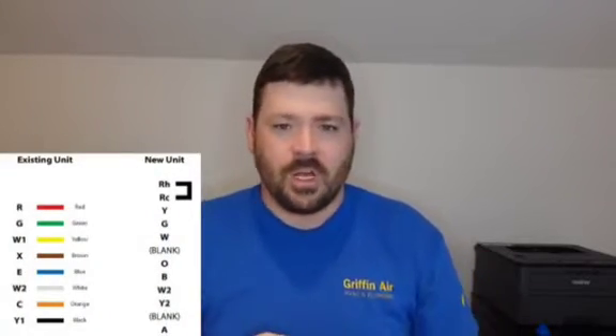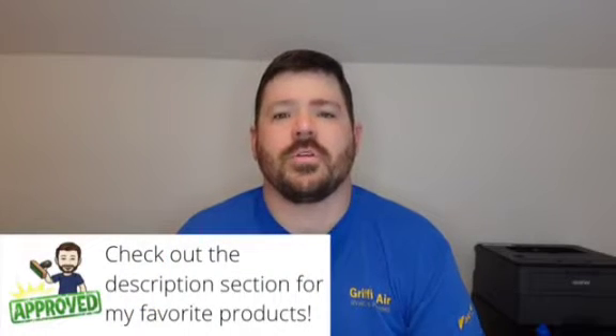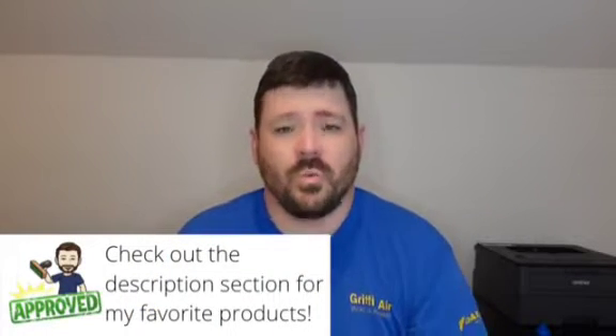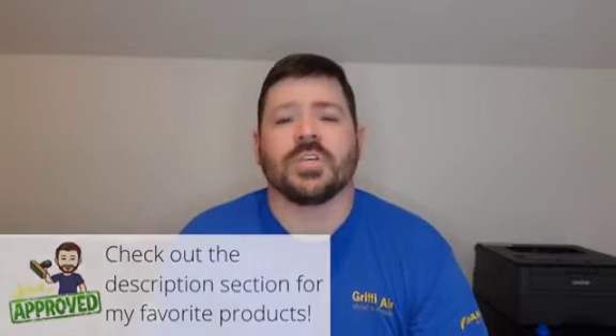When it comes to the common wire, I've noticed that different brands use different color common wires. Commonly, it's going to be usually black or blue. I have seen gray used before, but ultimately you want to keep that in mind if you are wiring in a new thermostat. Another example might be Trane and American Standard. When you're installing or replacing one of their thermostats, sometimes they'll have a B terminal, and a lot of folks will use the blue wire for that. But with just about every other thermostat on the market, B means something totally different. With Trane and American Standard, it's your common wire, but with those other thermostats, it's your reversing valve, energizing in heating mode.